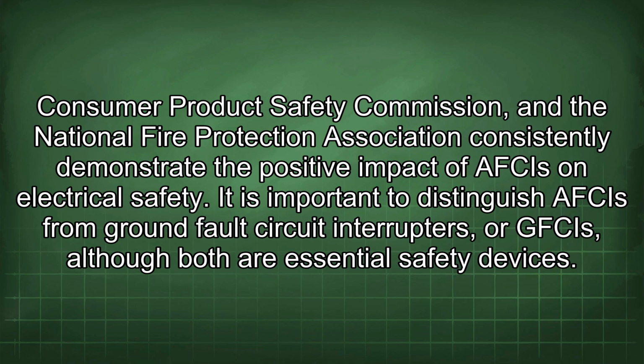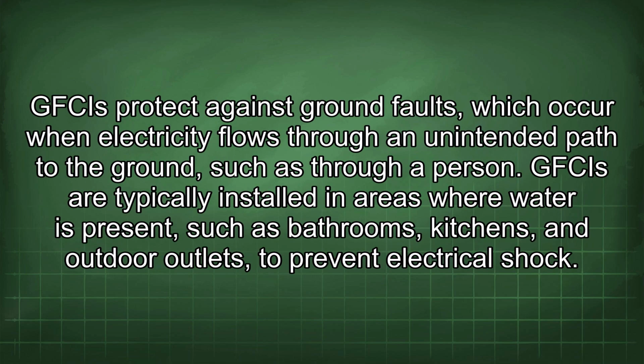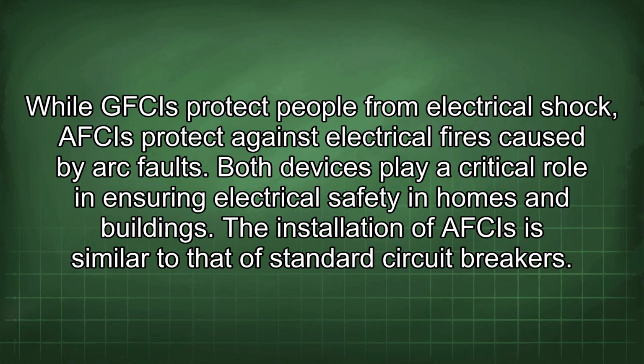Consumer Product Safety Commission, and the National Fire Protection Association consistently demonstrate the positive impact of AFCIs on electrical safety. It is important to distinguish AFCIs from ground fault circuit interrupters, or GFCIs, although both are essential safety devices. GFCIs protect against ground faults, which occur when electricity flows through an unintended path to the ground, such as through a person. GFCIs are typically installed in areas where water is present, such as bathrooms, kitchens, and outdoor outlets, to prevent electrical shock. While GFCIs protect people from electrical shock, AFCIs protect against electrical fires caused by arc faults. Both devices play a critical role in ensuring electrical safety in homes and buildings.